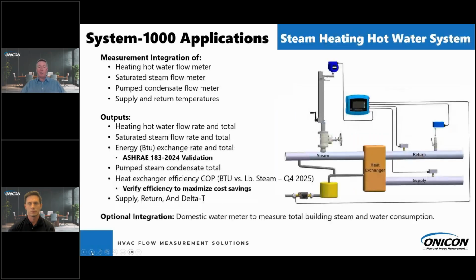Now this looks a little bit more complicated, so we're getting somewhere here. This is a steam heating hot water system with a heat exchanger. We're going to have a heating hot water flow meter. We'll have a saturated steam flow meter from ONICON on your steam pipe. We can have a pumped condensate flow meter down at the bottom. And of course, we'll have our supply and return temperatures. So in this type of system, we're still operating on just one channel of the System 1000.